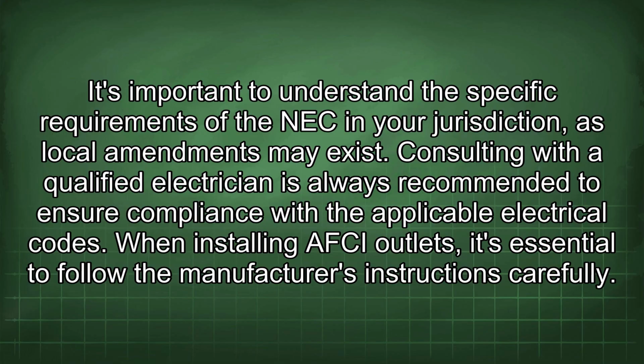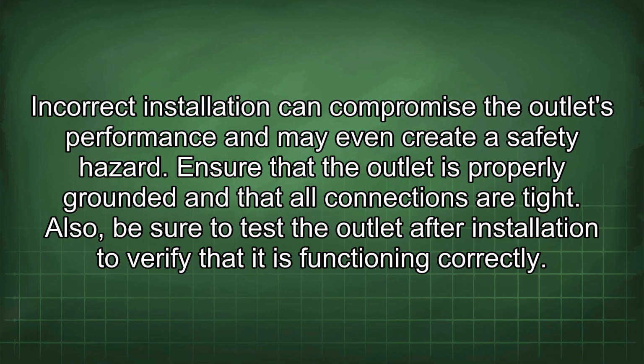Consulting with a qualified electrician is always recommended to ensure compliance with the applicable electrical codes. When installing AFCI outlets, it's essential to follow the manufacturer's instructions carefully. Incorrect installation can compromise the outlet's performance and may even create a safety hazard. Ensure that the outlet is properly grounded and that all connections are tight. Also, be sure to test the outlet after installation to verify that it is functioning correctly.